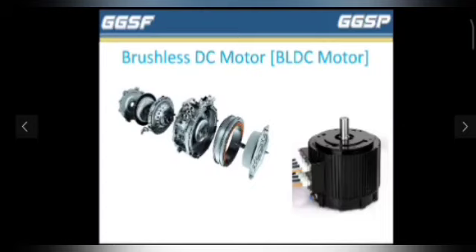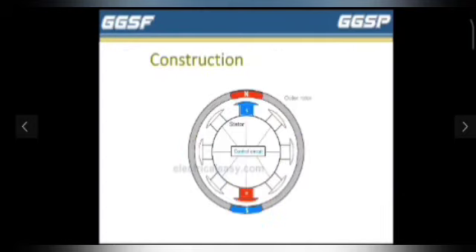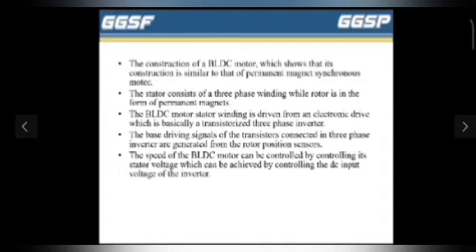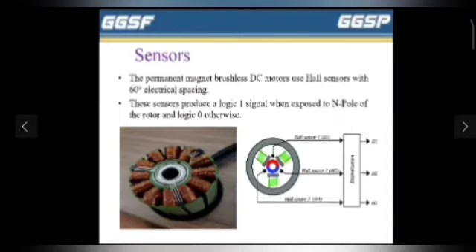BLDC motors, brushless DC motor. Construction. The construction of a BLDC motor is similar to the permanent magnet synchronous motor. The stator consists of three-phase winding, while the rotor is in the form of a permanent magnet. The stator winding is given supply from an electronic drive, which is basically a transistorized three-phase inverter. The speed of the BLDC motor can be controlled by controlling its stator voltage, which can be achieved by controlling the DC input voltage of the inverter.